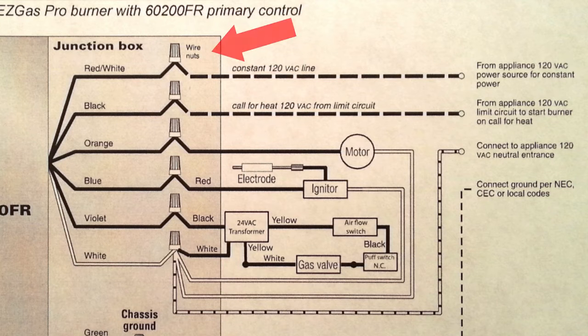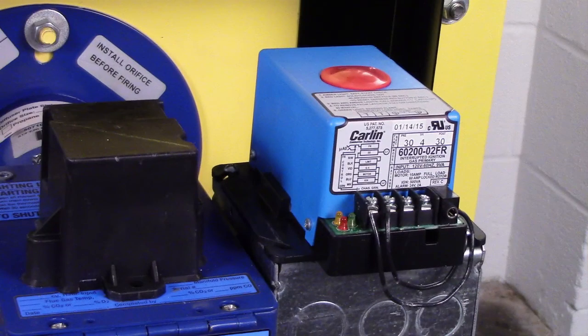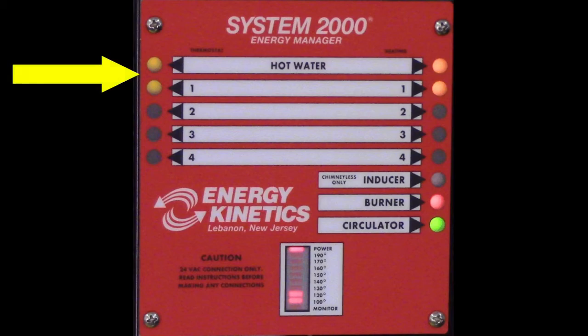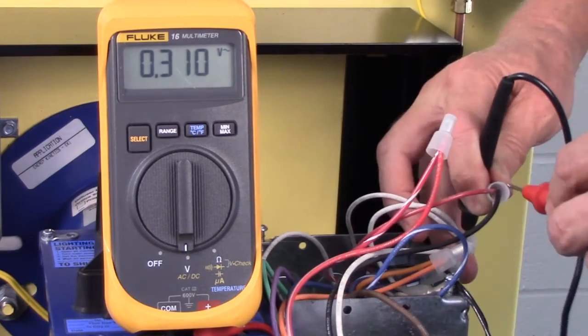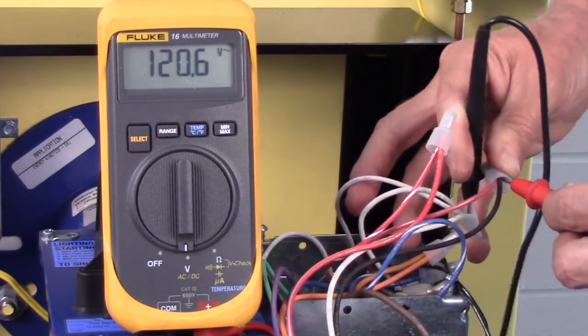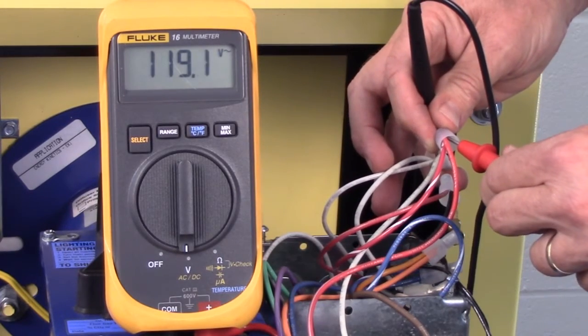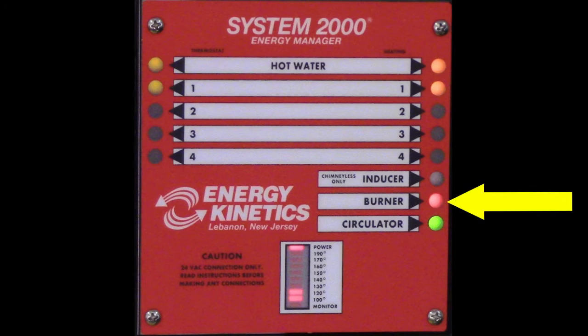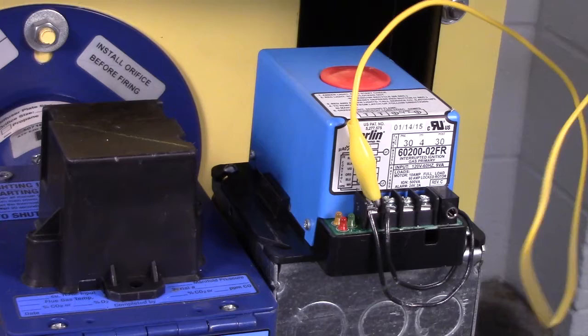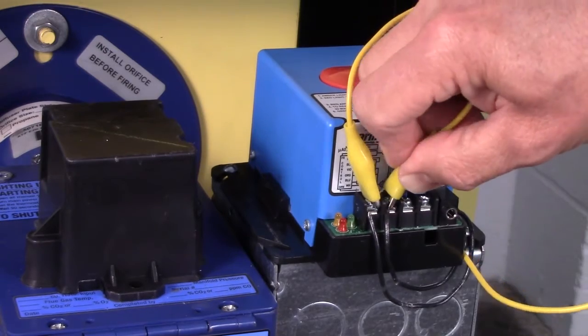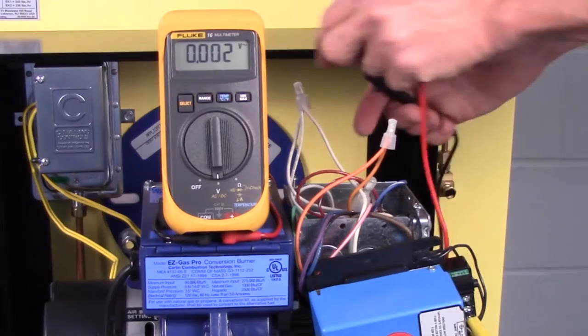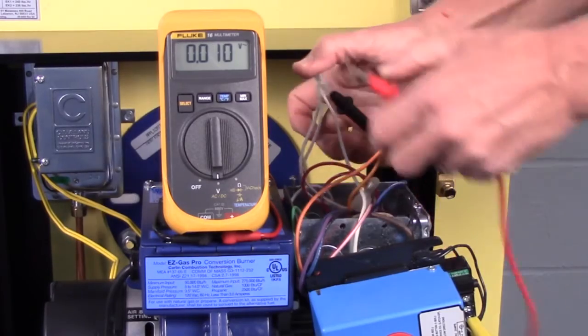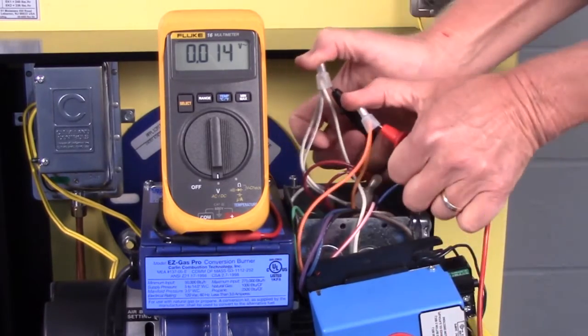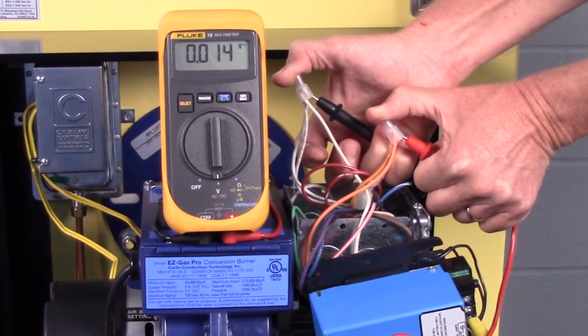The primary control's red with white stripe wire should be connected to a constant 120 volts AC power supply from the double pole burner switch. Check primary control operation by providing a call to the manager and check for 120 volts AC with a meter between both the black wire to neutral and then the red with white stripe wire to neutral. If the burner light on the manager is lit, but the motor does not start, install a jumper across the TT terminals. If the motor does not start, check for 120 volts AC between the orange motor lead and neutral. If there is no voltage to the motor lead, the control is defective and needs to be replaced.